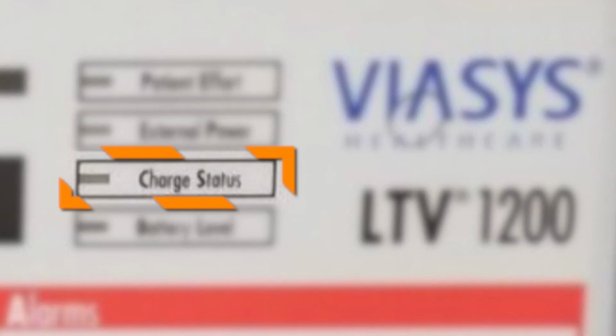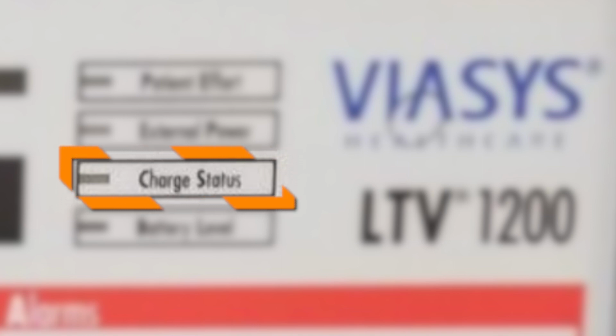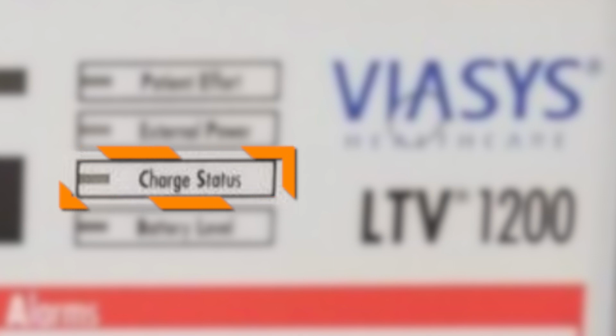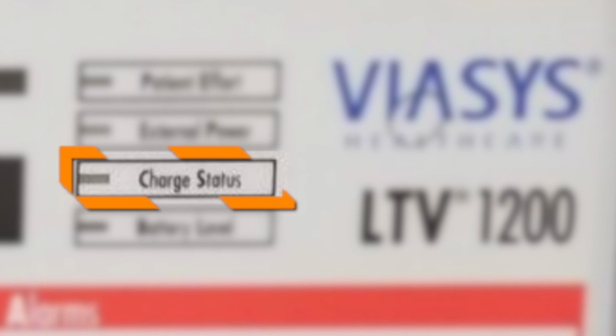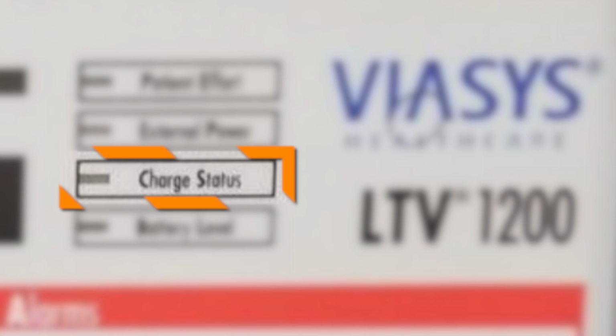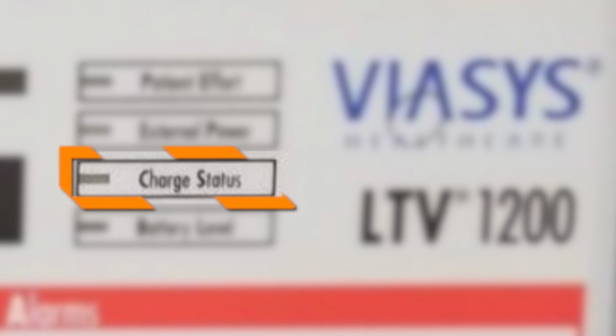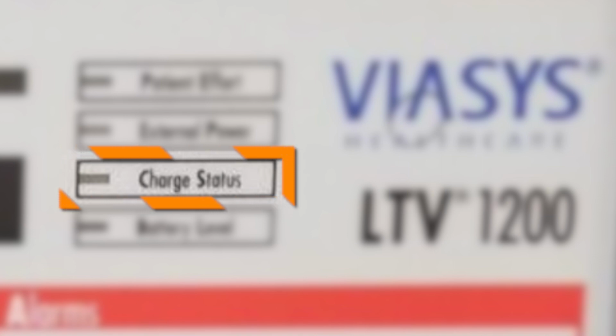Charge status. When the ventilator is plugged into an external power source, it automatically charges the internal battery. If the LED color is flashing amber, this means the ventilator is performing pre-charge qualification testing of the battery prior to starting the charge process. If it's green, the internal battery is charged to full level. Amber means the battery has not reached a full charge level and is still charging, and red means the ventilator has detected a charge fault or internal battery fault.